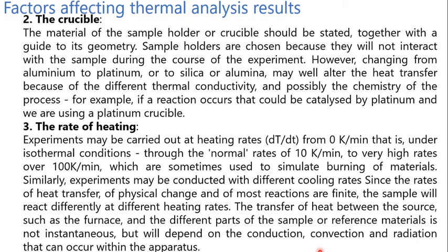Then the third one, the rate of heating. Experiments may be carried out at heating rates from 5 degrees to 10 degrees per minute, or under isothermal conditions, through the normal rates of 10 Kelvin per minute to very high rates over 100 Kelvin per minute, which are sometimes used to simulate burning of the materials.